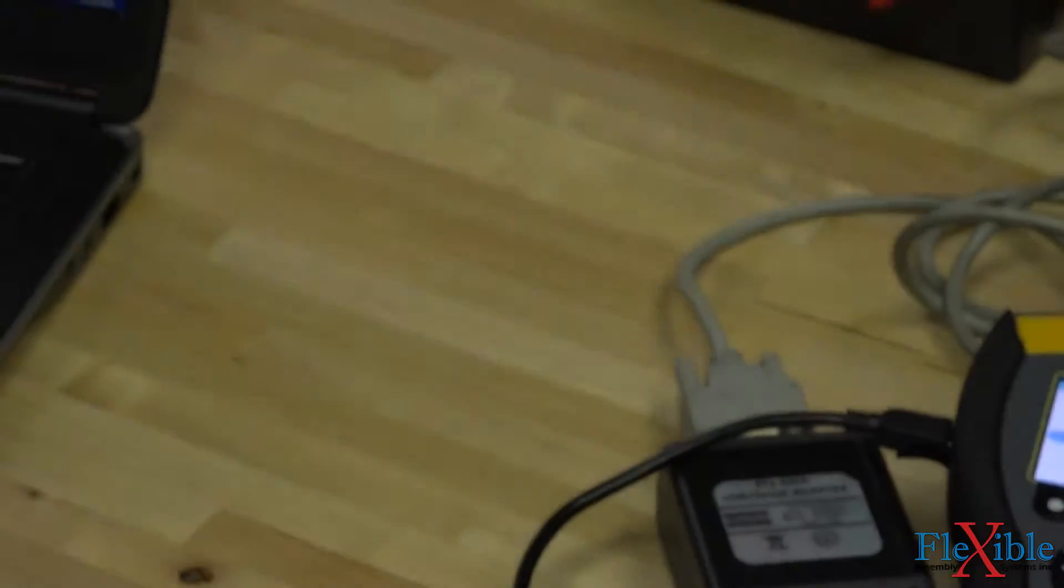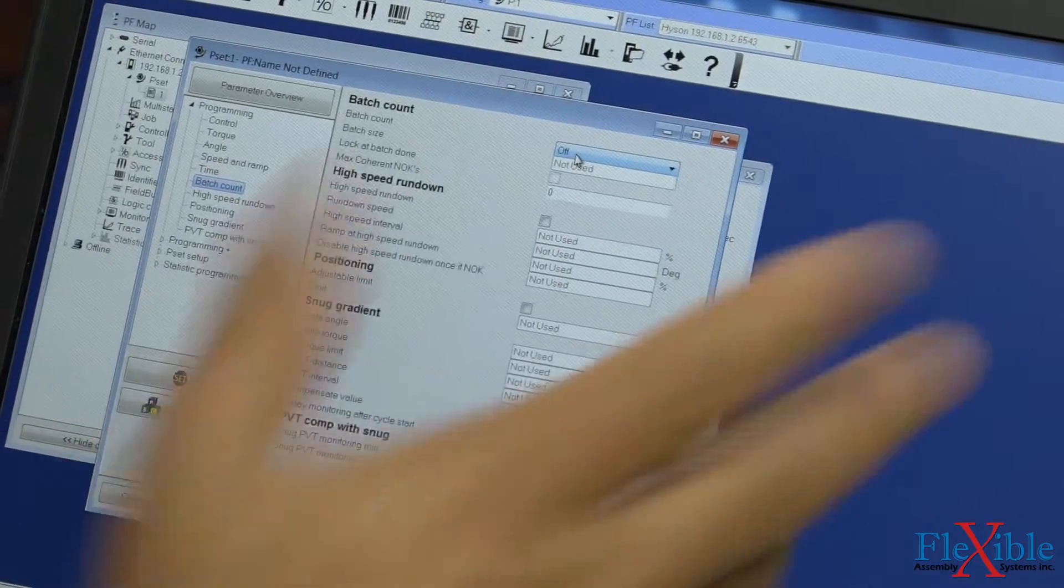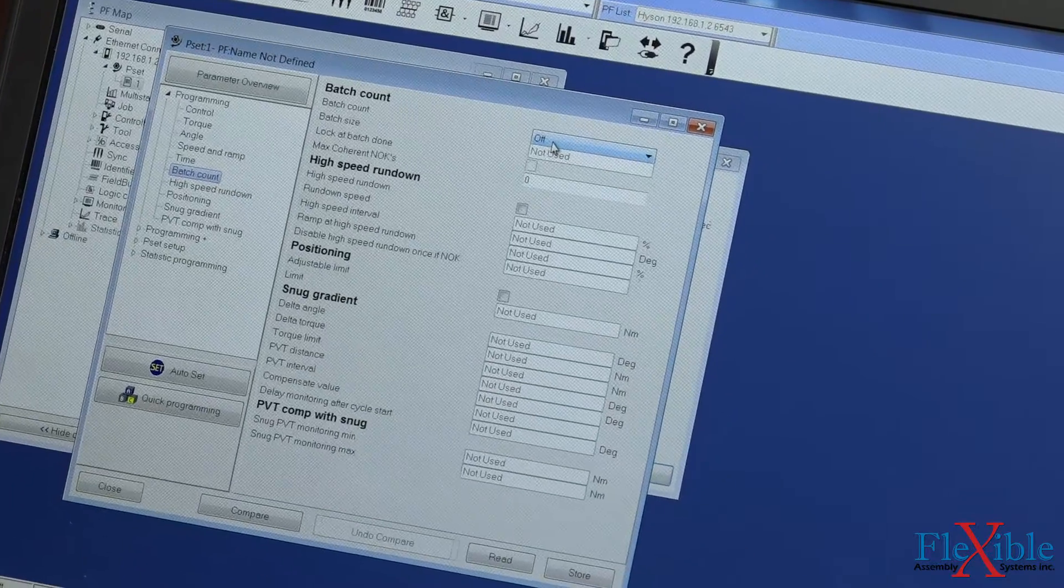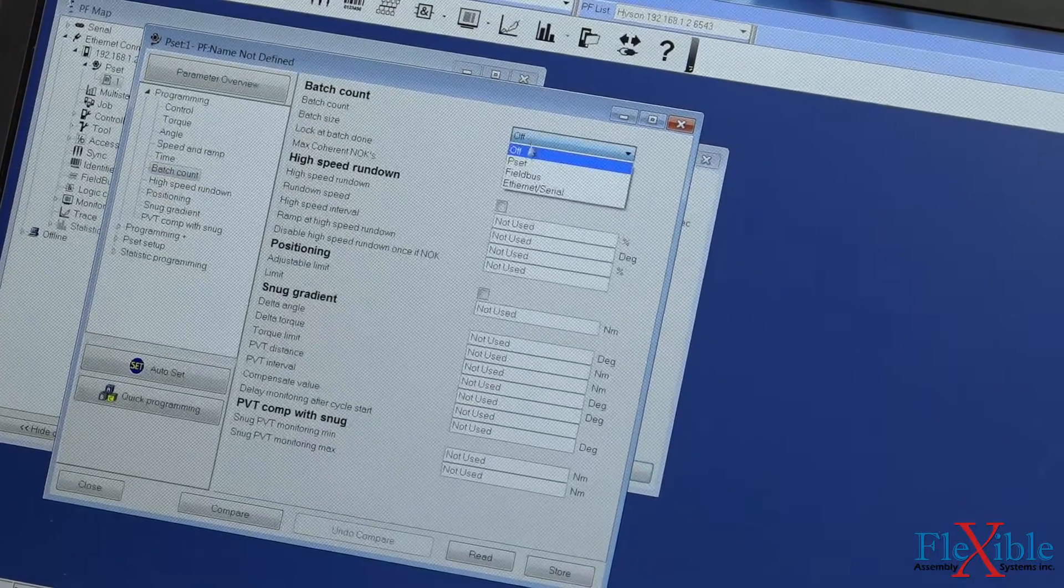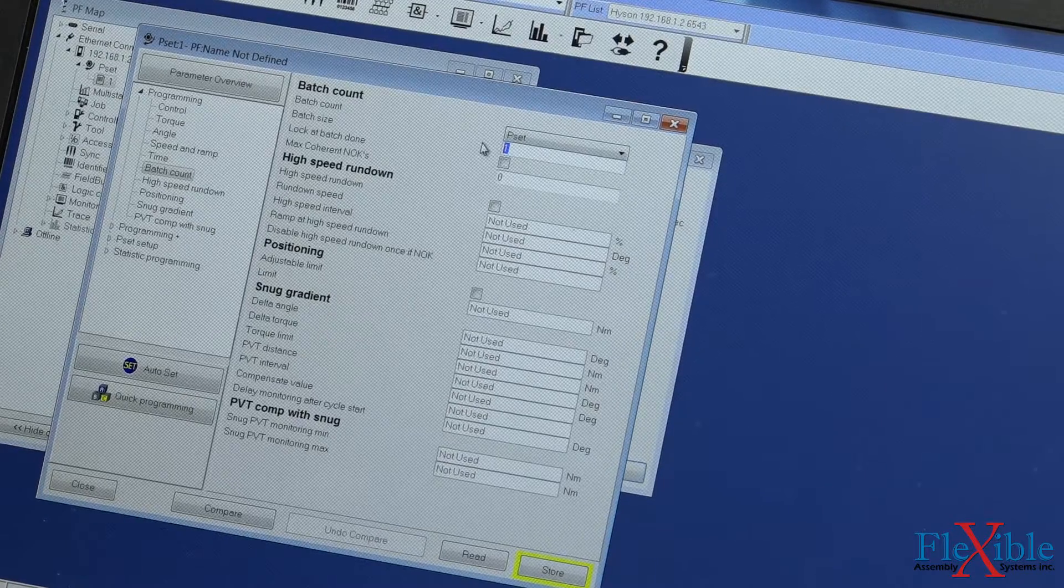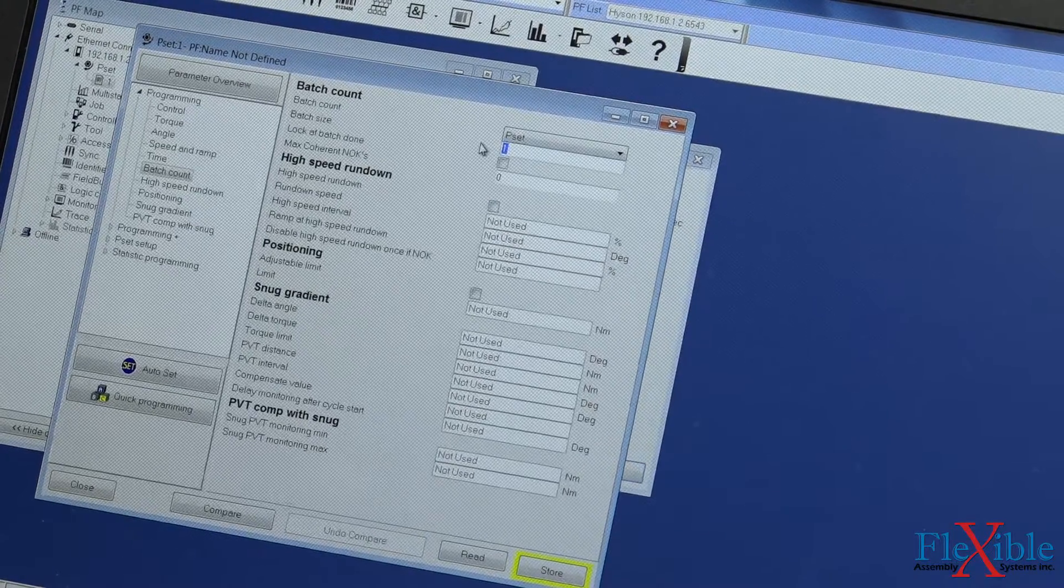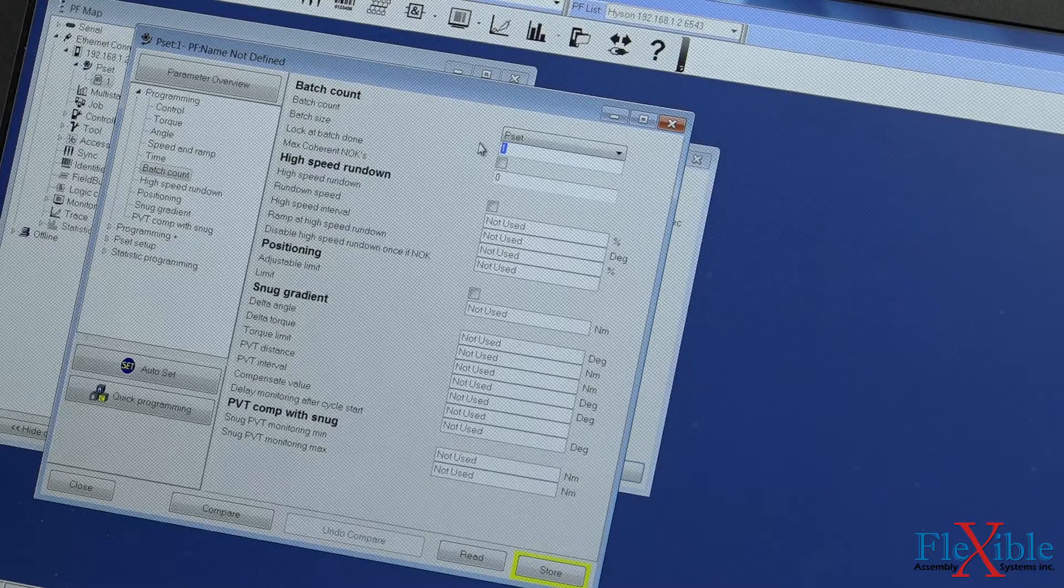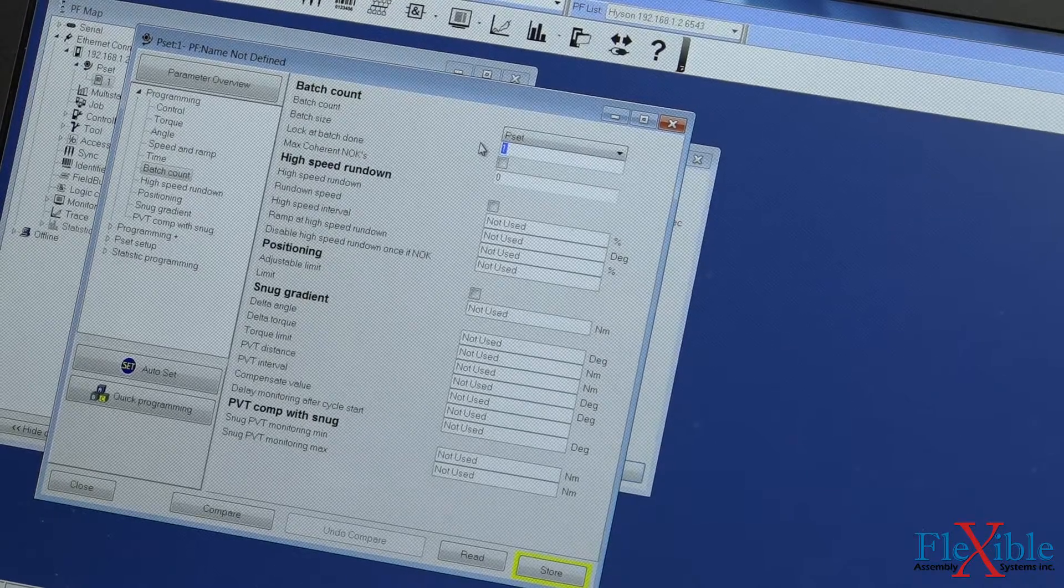To remedy this, we must change our batch count in ToolsTalk PF or directly on the controller if you have a graph model. The calibration needs a minimum of 3 results to be able to calculate a proper calibration value. We change ours to 3 for a quick calibration and then click Store to save our PSET.